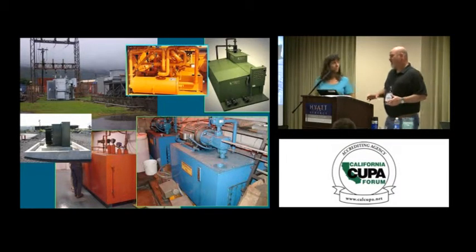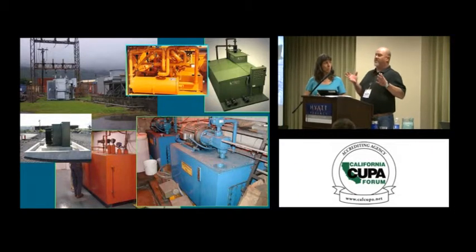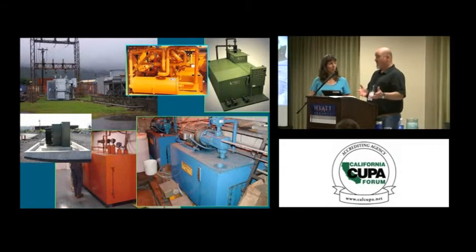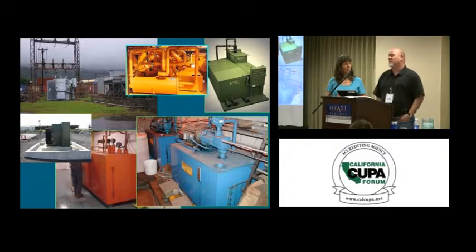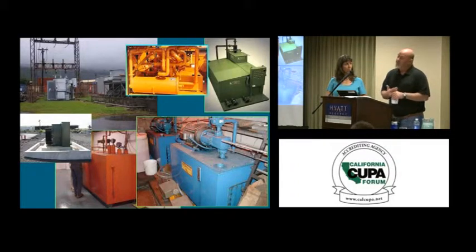I would also try and clarify that it would have to be a case scenario for the day tank and how it's designed, its capacity, how it's fed, what its valving and controls are, where it sits in the line. Those would be determinations that would be looked at. Okay, it's a day tank, but the way it's configured is part of the transfer piping system, and it's not really more than that, then general containment would apply. But if that day tank was significantly sized and had controls on either side, it may be a bulk storage container in its own right.